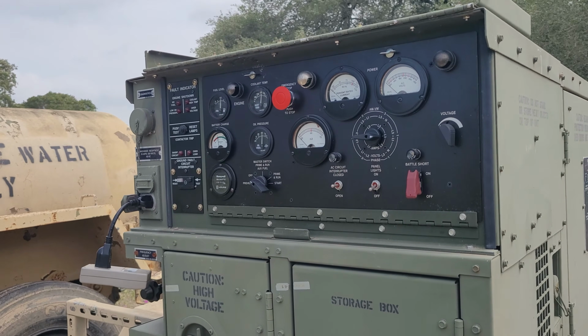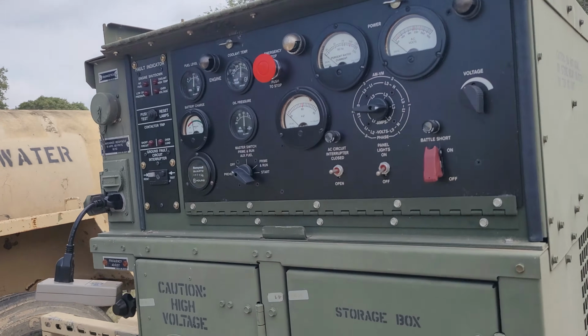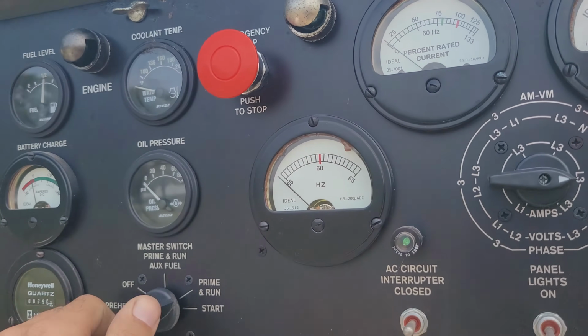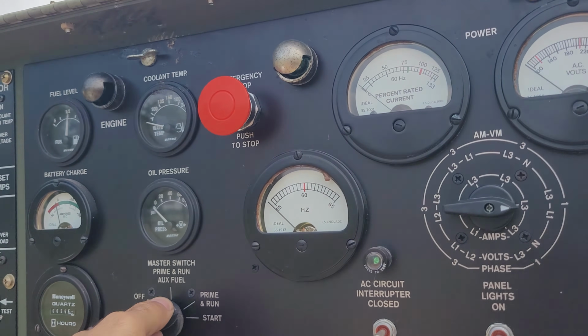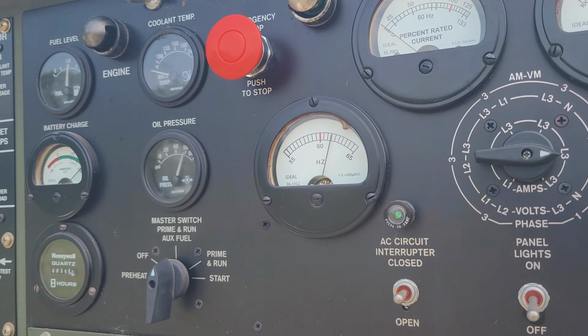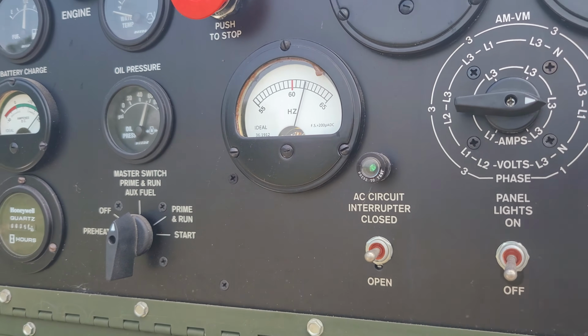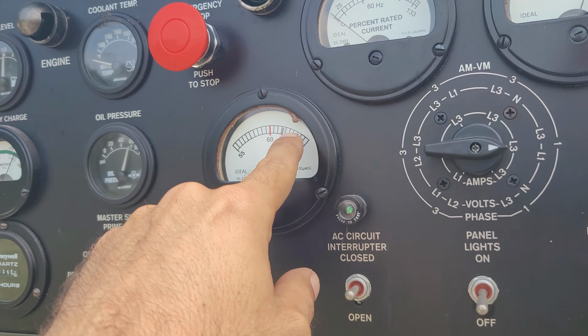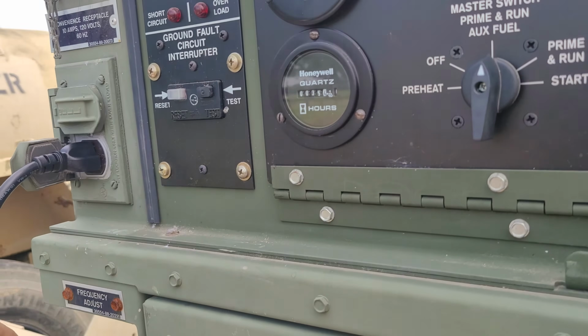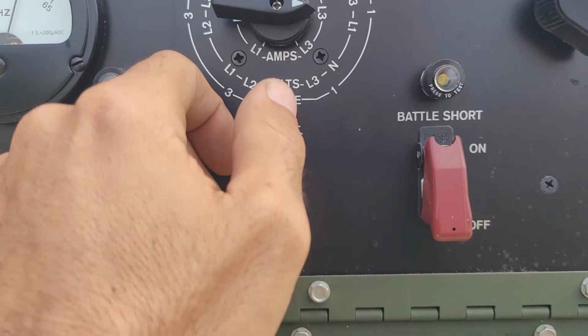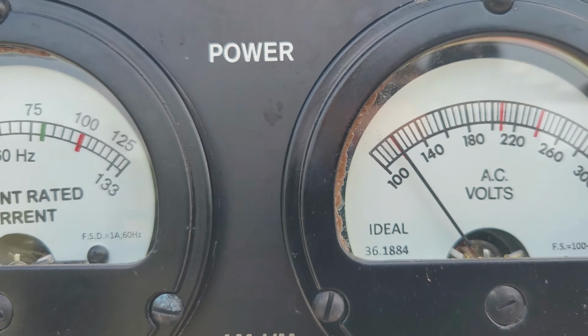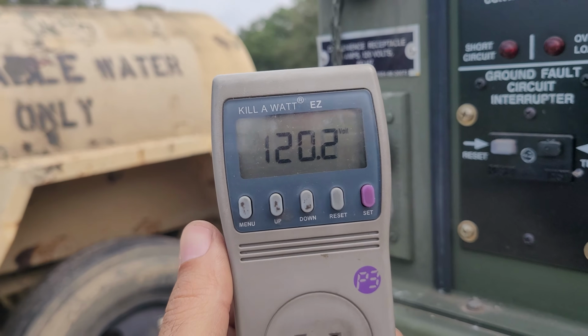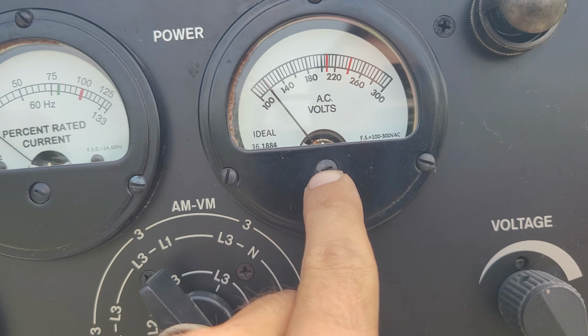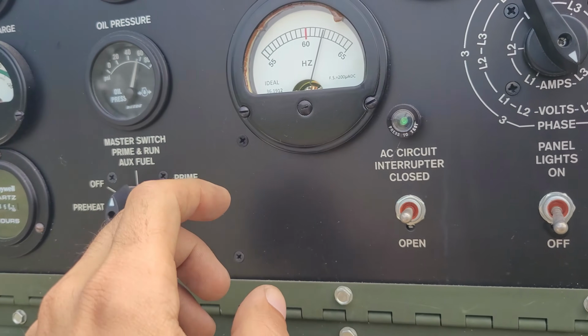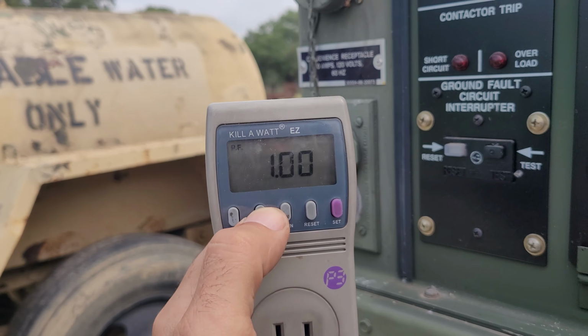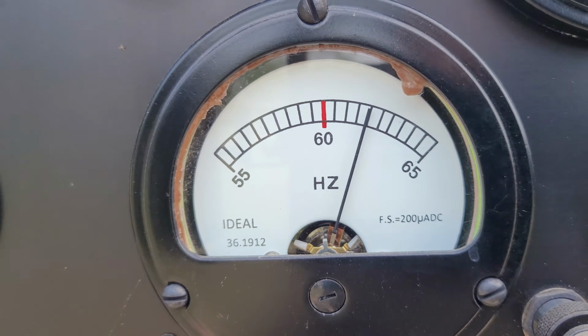Start it, get your gauges where they need to be, check against them, and let it warm up. Generally at 100% load you want your hertz gauge around here. As it's warming up, you can move this switch to check voltage, 120 volts, cool. If that's off, you can use a little flathead screwdriver and adjust these, just be careful. Checking the hertz now, about right, 62, there you go.